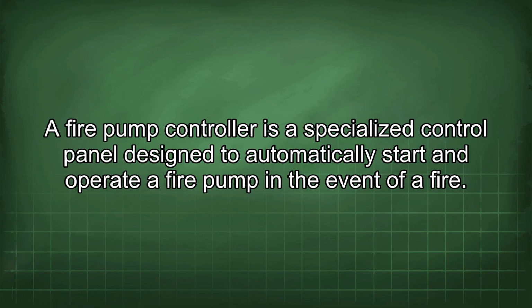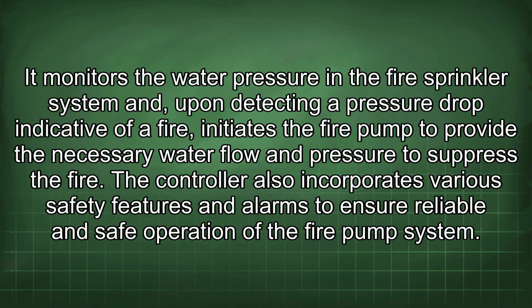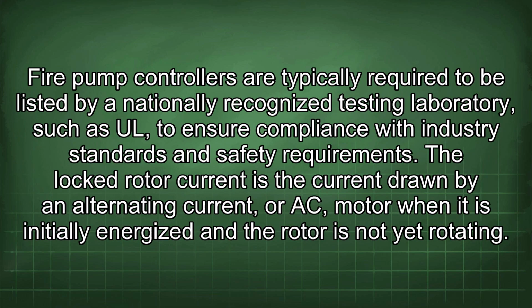A fire pump controller is a specialized control panel designed to automatically start and operate a fire pump in the event of a fire. It monitors the water pressure in a fire sprinkler system and, upon detecting a pressure drop indicative of a fire, initiates the fire pump to provide the necessary water flow and pressure to suppress the fire. The controller also incorporates various safety features and alarms to ensure reliable and safe operation of the fire pump system. Fire pump controllers are typically required to be listed by a nationally recognized testing laboratory such as UL to ensure compliance with industry standards and safety requirements.